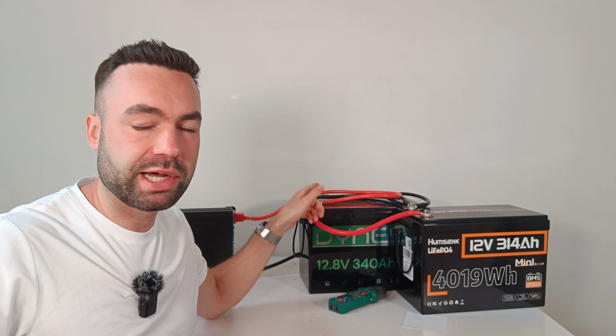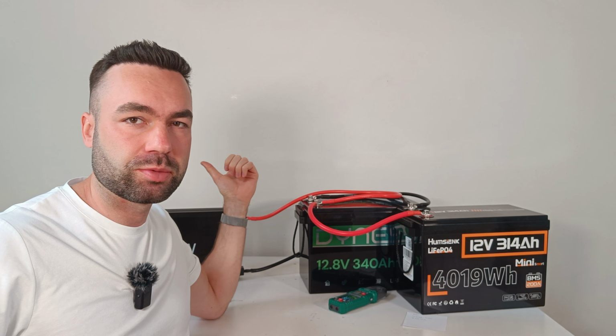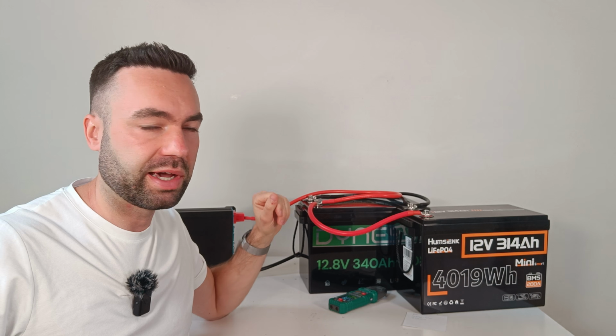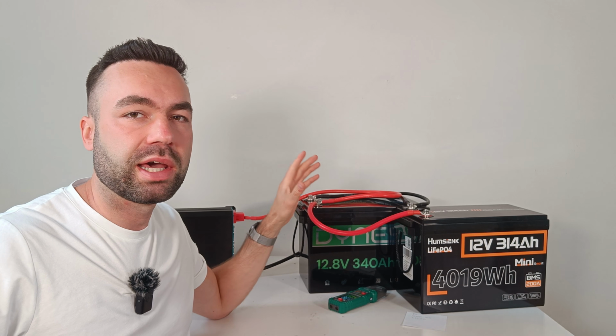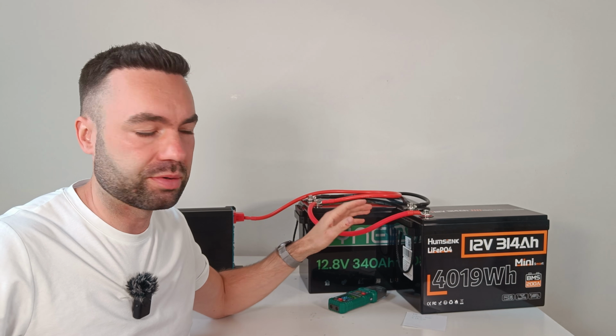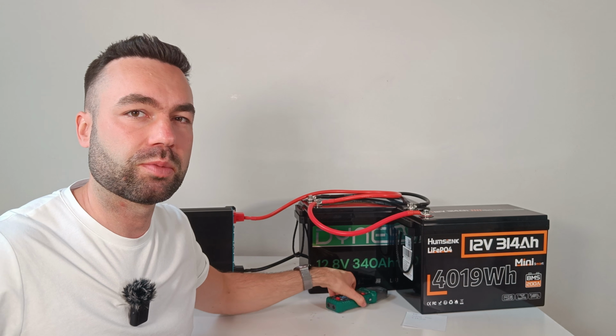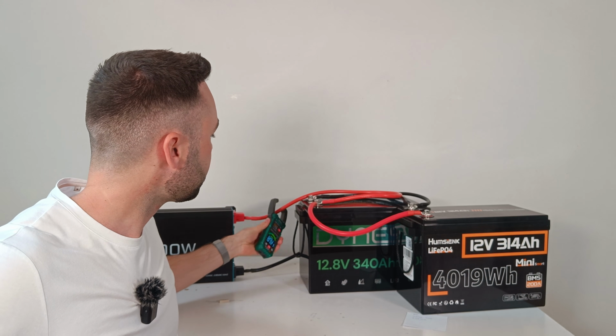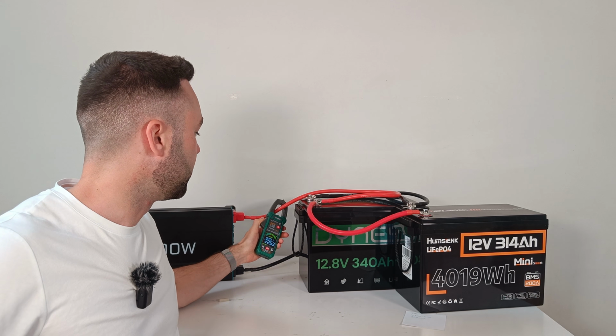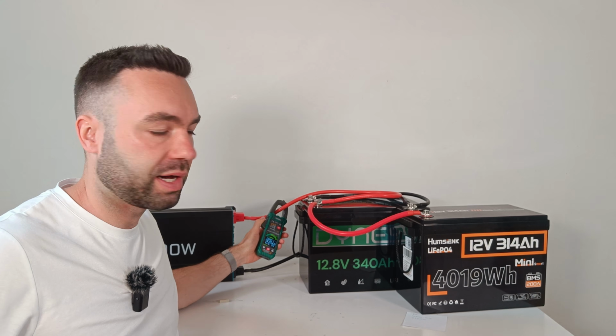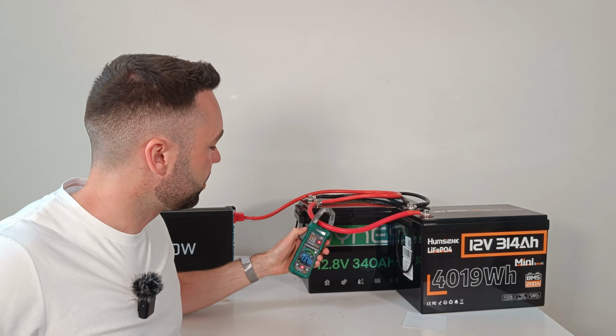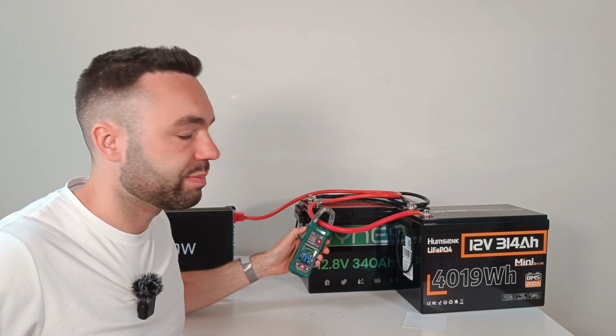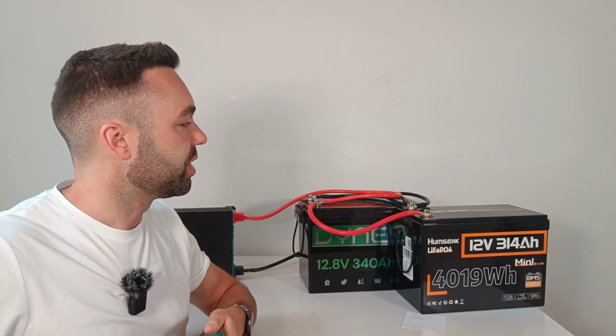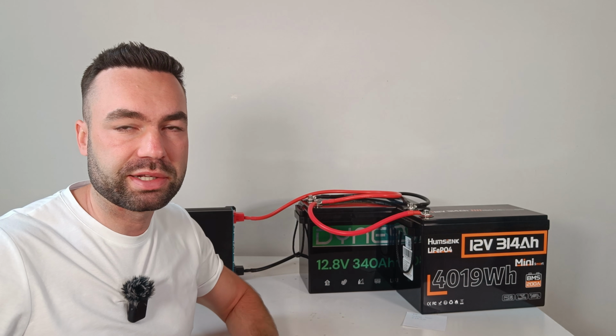I have added another battery in parallel and connected to an inverter with a small 20 amp load. I will check if this battery is sharing the current, because that was a problem with smart batteries. The total current draw is 22.5 amps and the other battery is delivering 13.7 amps, so this battery is sharing the current correctly.